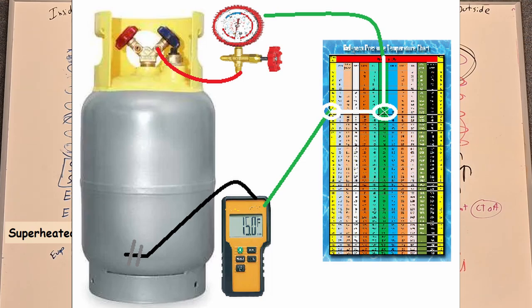So instead of a pump-down, take all the refrigerant out into its own dedicated recovery tank — with liquid and vapor together in that tank. Let it sit and equalize, then get the temperature of the tank with a thermometer on the bottom liquid side and hook a pressure gauge to it. Now you know both the pressure and temperature of the tank and know what refrigerant is supposedly in it. Pull out your temperature-pressure chart app and compare — the pressure and temperature should match. If they match, you don't have non-condensibles. If they don't match, you have non-condensibles and contaminants.